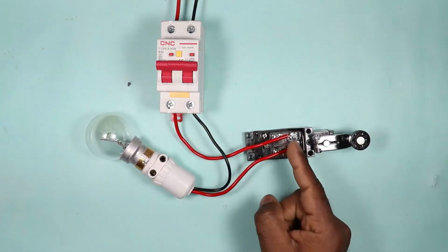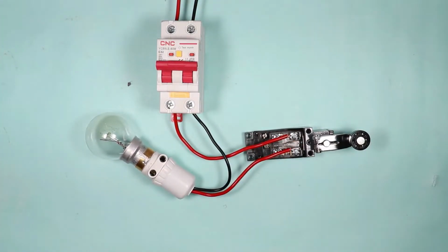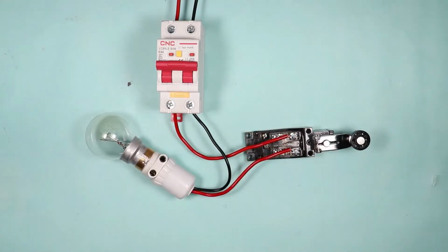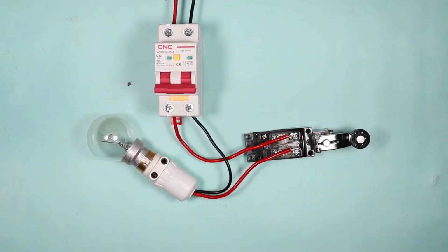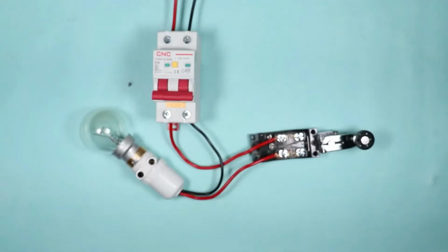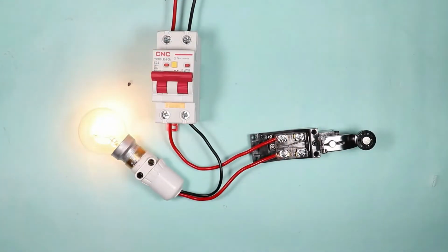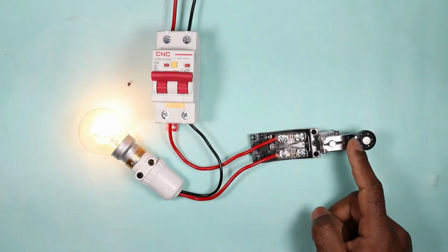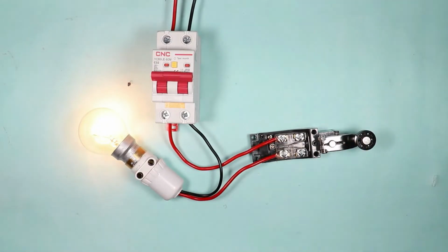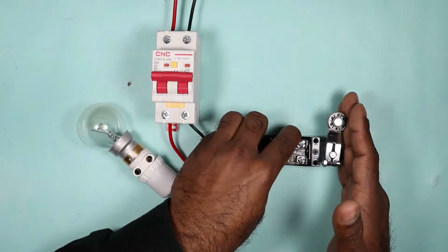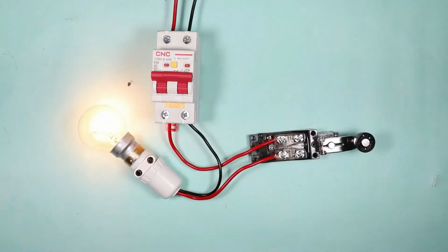On operating through NO contact, if the limit switch does not operate, then this lamp or signal will not be generated. Now if you use the NC contact of the limit switch, let's change the connection fast. So now I connected the wires at NC contact. When I turn on this MCB, you can see the lamp is in on condition. This means the output command is generated by the limit switch. When an object touches the switch in this way and there is a movement in the plunger, then the lamp will turn off. On releasing the plunger, the lamp will again turn on.